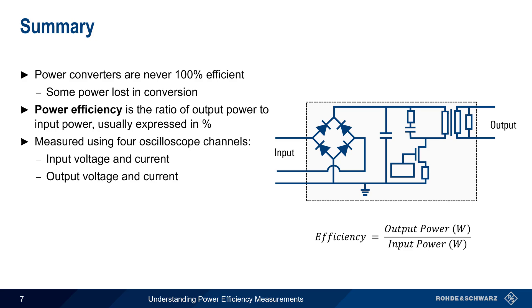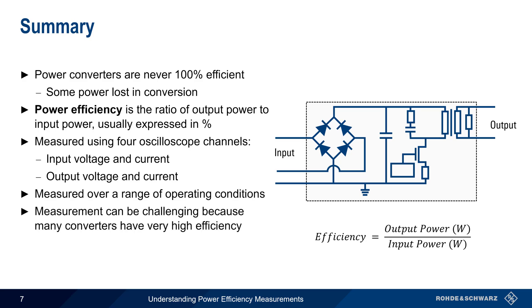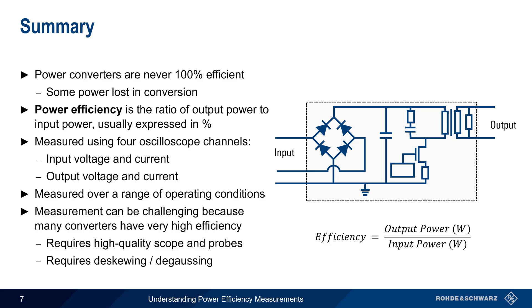Because efficiency often changes depending on operating conditions, it's commonly measured over a range of input voltages for different loads. Although it's a relatively simple measurement, the high efficiency of many modern power converters makes this measurement challenging. High accuracy is needed in both the oscilloscope as well as the probes, and procedures such as deskewing, degaussing, and zeroing are also important in obtaining accurate, repeatable measurements.